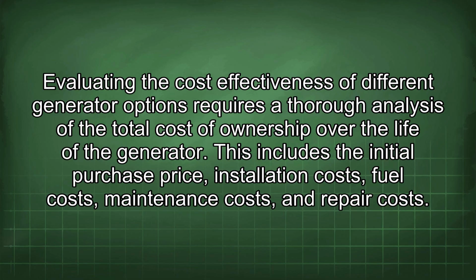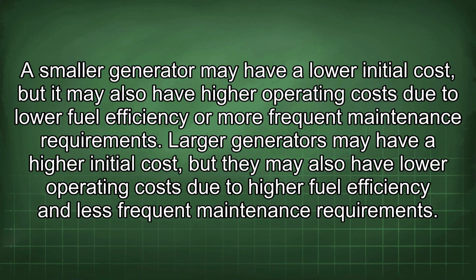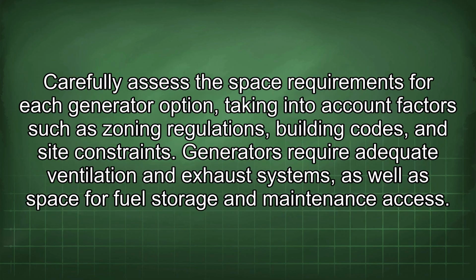Evaluating the cost-effectiveness of different generator options requires a thorough analysis of the total cost of ownership over the life of the generator. This includes the initial purchase price, installation costs, fuel costs, maintenance costs, and repair costs. A smaller generator may have a lower initial cost, but it may also have higher operating costs due to lower fuel efficiency or more frequent maintenance requirements. Larger generators may have a higher initial cost, but they may also have lower operating costs due to higher fuel efficiency and less frequent maintenance requirements. Carefully assess the space requirements for each generator option, taking into account factors such as zoning regulations, building codes, and site constraints.